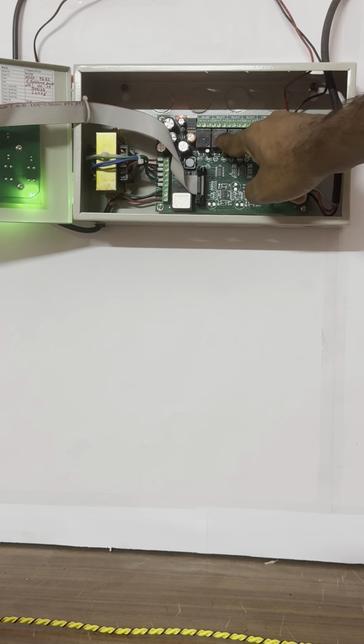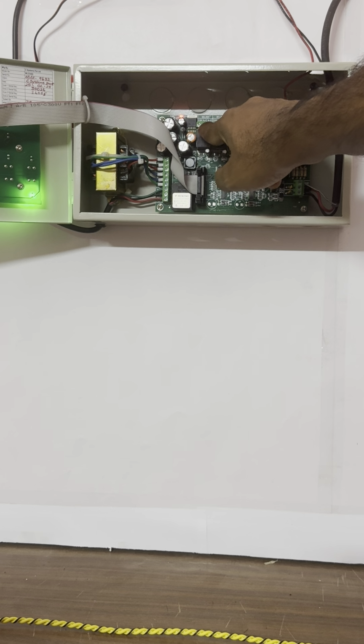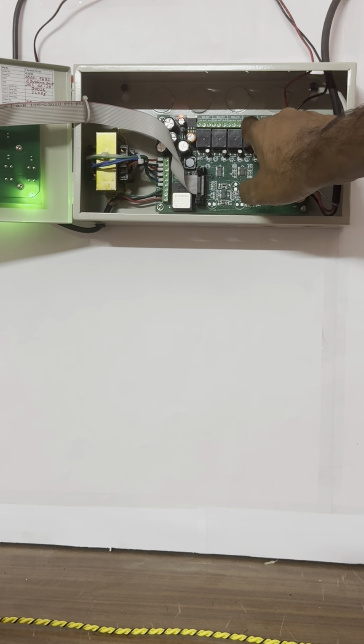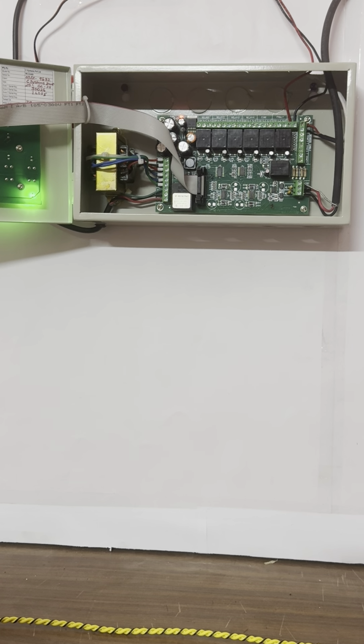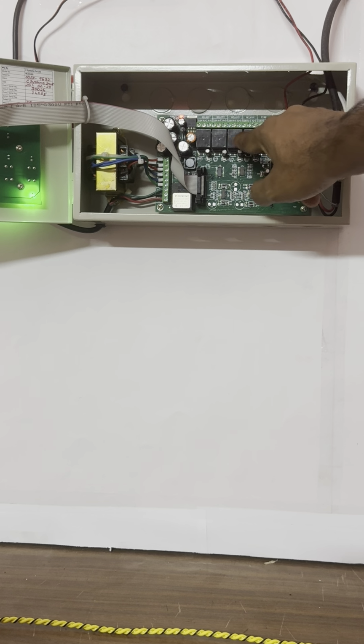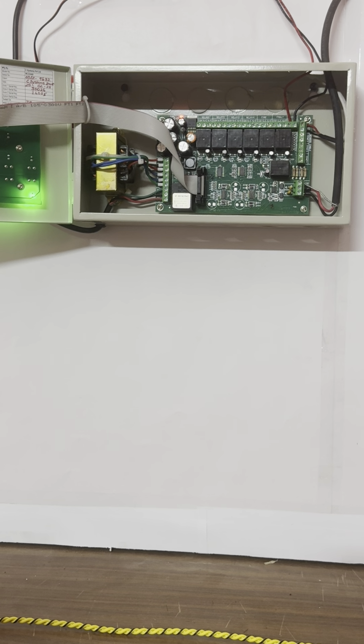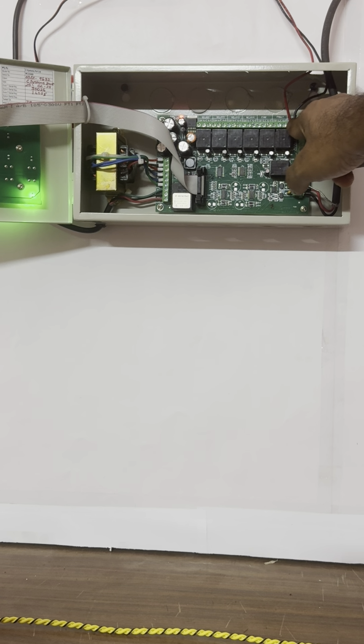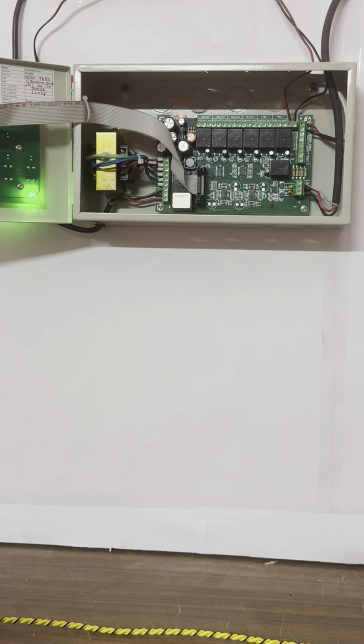The output of the zones can be read out by the relay outputs, relay 1, relay 2, relay 3 and relay 4. These are the dedicated relay outputs for each zone input. Whenever an alarm is triggered in the respective zone, the respective relay will get activated. Apart from the individual relay outputs, there is a common fire output which can be integrated for fire integration, and there is a common fault output for reading it in the BMS or in the fire panel. There is a dedicated hooter output which delivers 12 volts DC supply. A hooter or hooter cum strobe can be connected to the terminal in order to get a hooter output whenever there is an alarm detected by the water leak sensor cable.